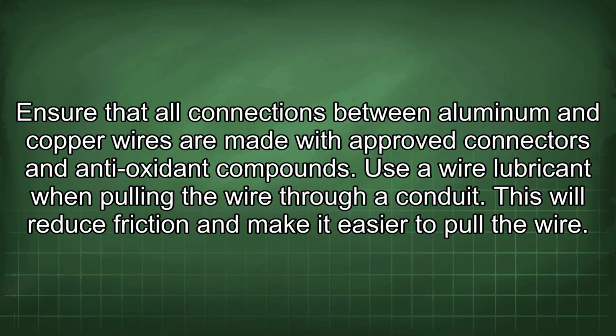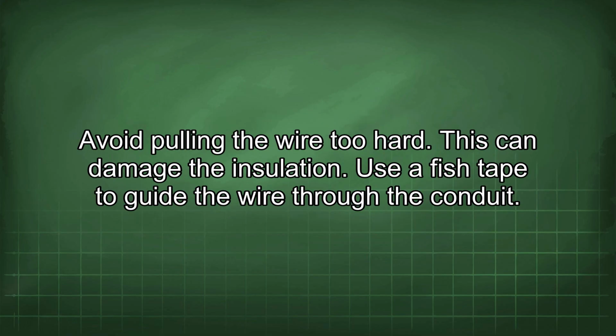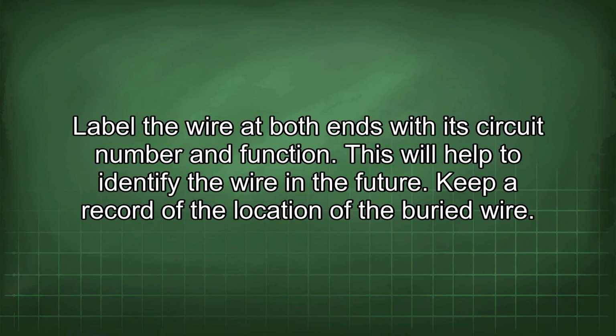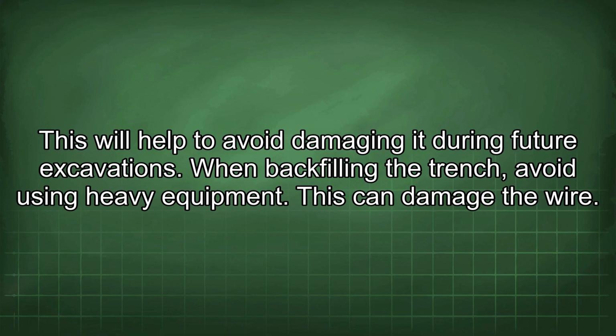Use a wire lubricant when pulling the wire through a conduit. This will reduce friction and make it easier to pull the wire. Avoid pulling the wire too hard. This can damage the insulation. Use a fish tape to guide the wire through the conduit. Label the wire at both ends with its circuit number and function. This will help to identify the wire in the future. Keep a record of the location of the buried wire. This will help to avoid damaging it during future excavations.